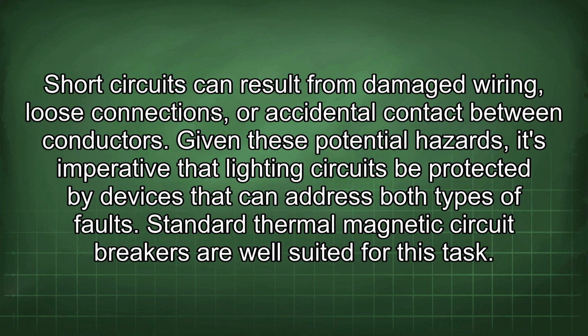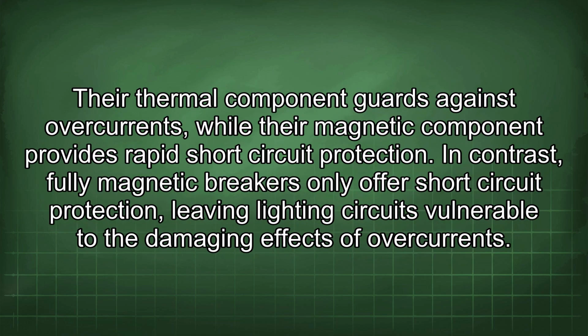Given these potential hazards, it's imperative that lighting circuits be protected by devices that can address both types of faults. Standard thermal magnetic circuit breakers are well suited for this task. Their thermal component guards against overcurrents, while their magnetic component provides rapid short-circuit protection. In contrast, fully magnetic breakers only offer short-circuit protection, leaving lighting circuits vulnerable to the damaging effects of overcurrents.